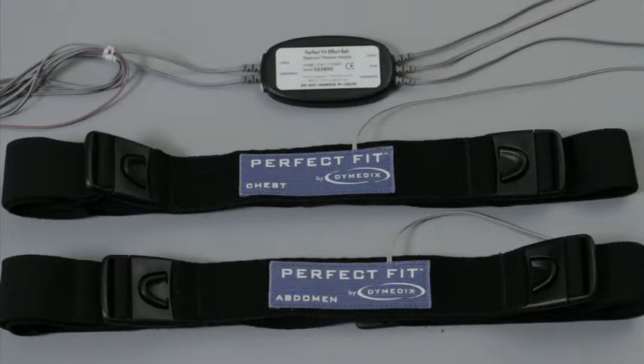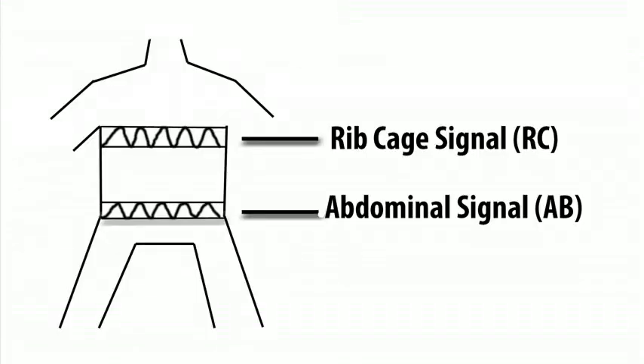Another bodily function measured in a sleep study is respiratory effort. While it can be measured with intercostal electrodes, it is most often measured with a band around the chest and one around the abdomen called respiratory effort belts. Respiratory inductance plethysmography, or RIP, consists of a band with a wire embedded in it that goes completely around the body. In its calibrated form, it is capable of showing that and a number of other detailed data. Unfortunately, as a patient moves around during a sleep study, it must be recalibrated. This necessitates the waking of the patient, and it is not practical for an everyday sleep study. Most labs use these belts uncalibrated. The other problem with RIP belts occurs as the wire inside is stretched over and over with each breath. Wire fatigue is reported by many labs, producing a noisy signal after a short period of repeated use.